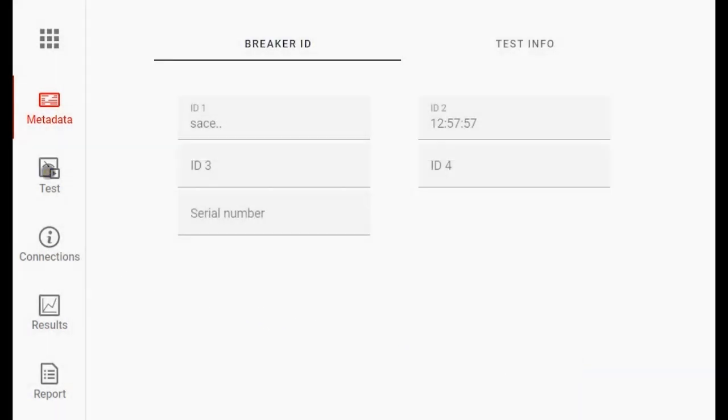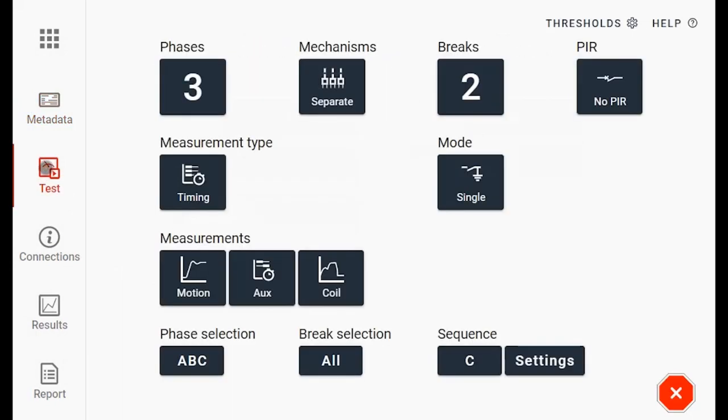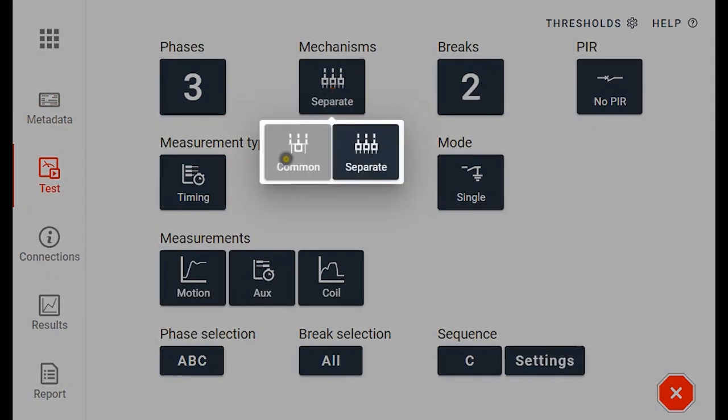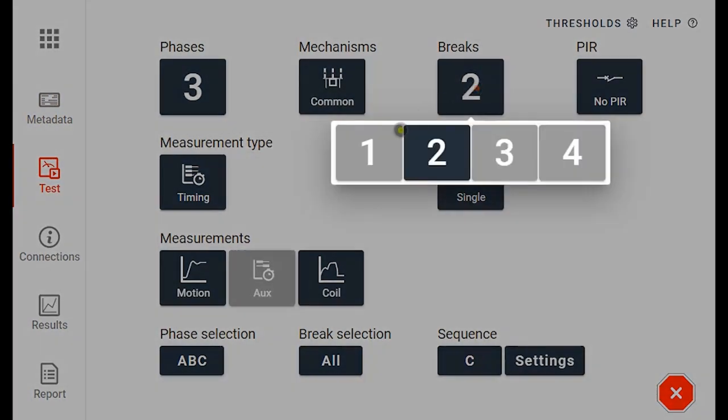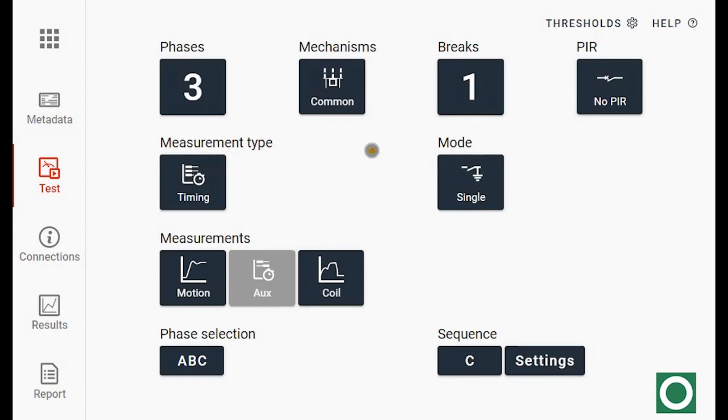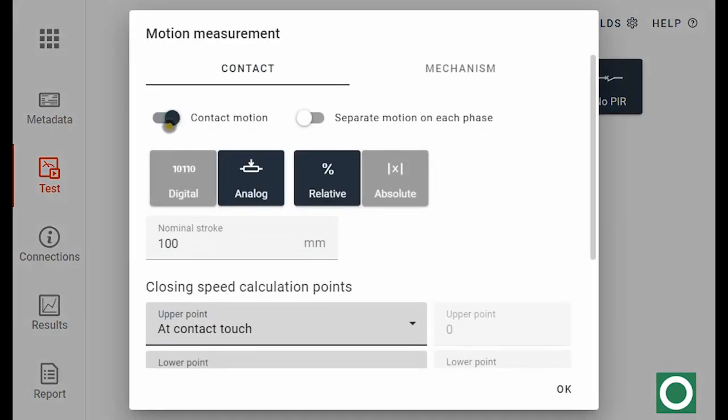I go to Test under Metadata to adjust my object. I have a smaller breaker, a common mechanism, and I only have one break. I want to measure timing and I want to do a motion measurement. So I have contact motion, analog, and I want to have 100 mm as a stroke.